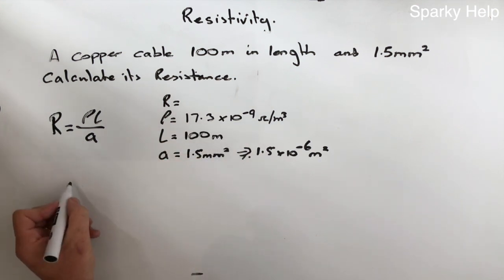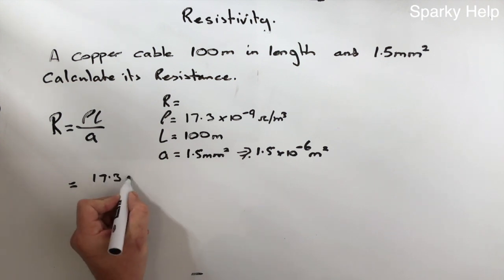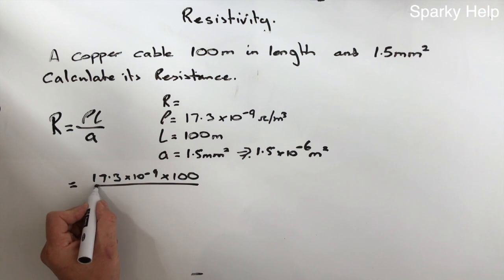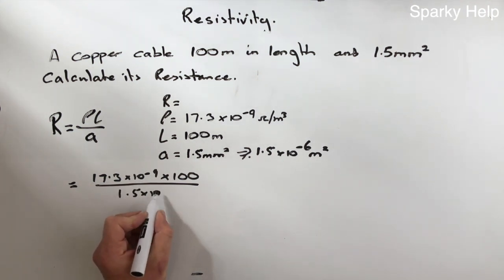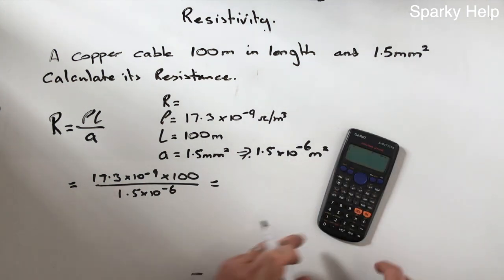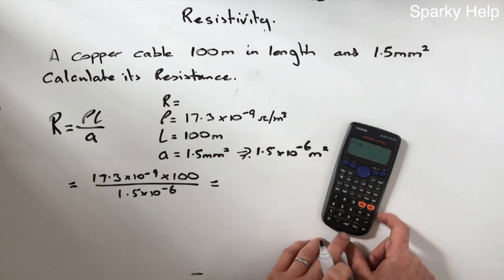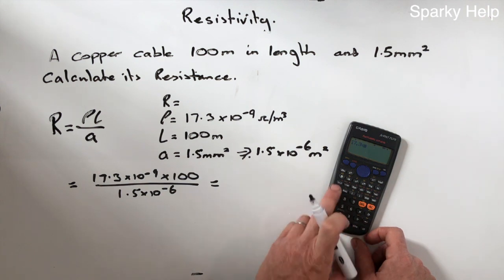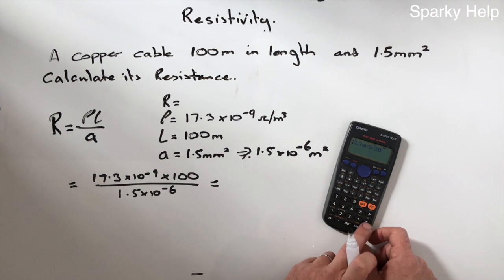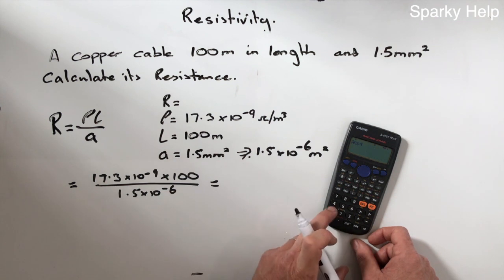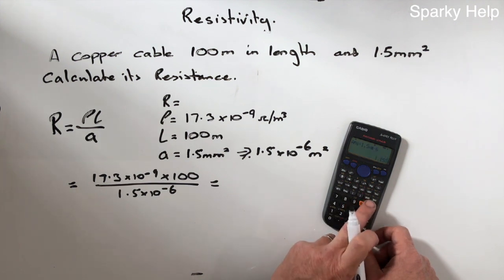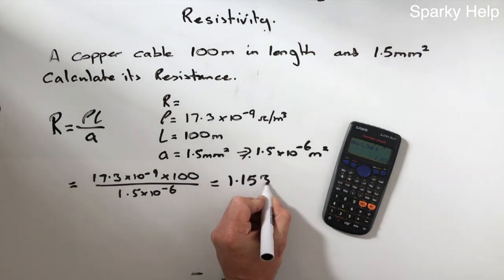So this is what we need to convert it to. Once we know these figures, we can now put them in over here. So rho, which is 17.3 times 10 to the minus 9, so it's a very small number. Multiplied by the length, which is 100. And then we divide that by this figure here, 1.5 times 10 to the minus 6. So in our calculator, remember 17.3, and we're going to use this button here, times 10 to the power of minus 9 times 100. As the top line comes to that, we're going to divide that number by 1.5 times 10 to the minus 6. And we get 1.153 ohms.